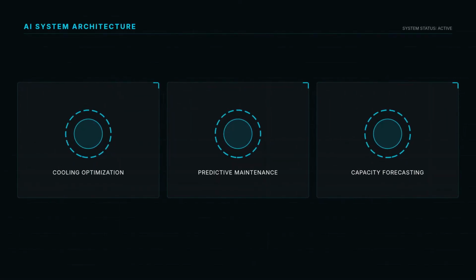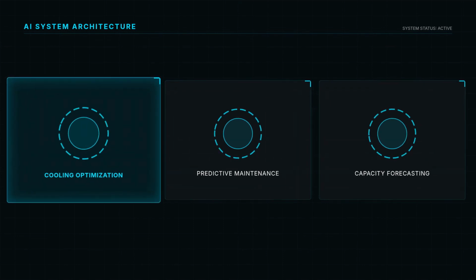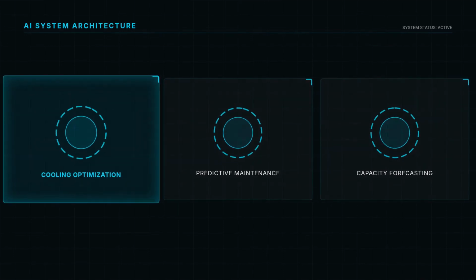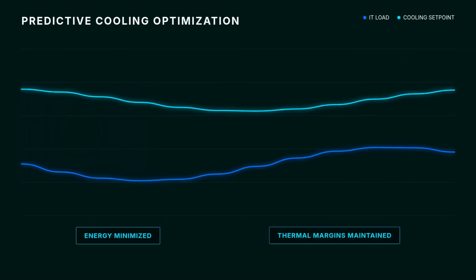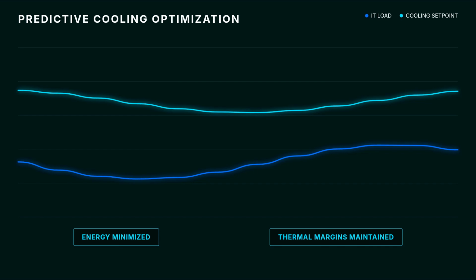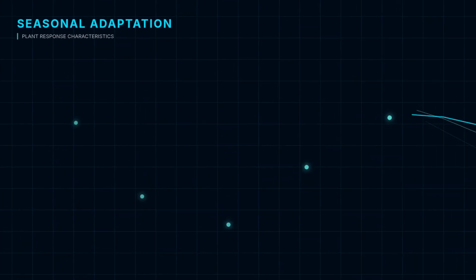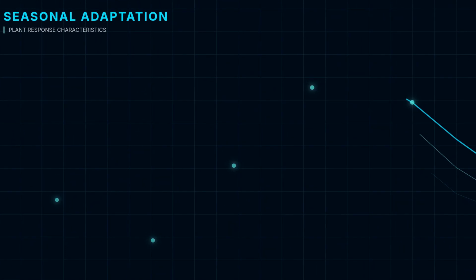Our DCIM also includes an AI capacity management module trained on 18 months of operational data. The AI does three things that rule-based systems simply cannot match, starting with predictive cooling optimization. The AI analyzes the relationship between IT load and outdoor temperature to continuously optimize cooling set points. It learns seasonal patterns and the specific response characteristics of every individual piece of cooling plant.